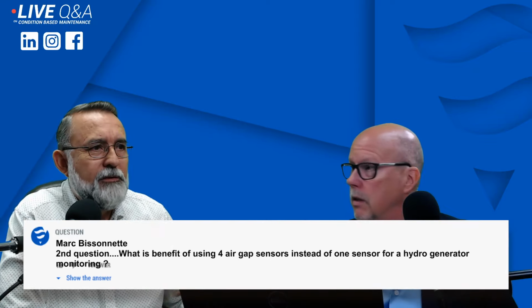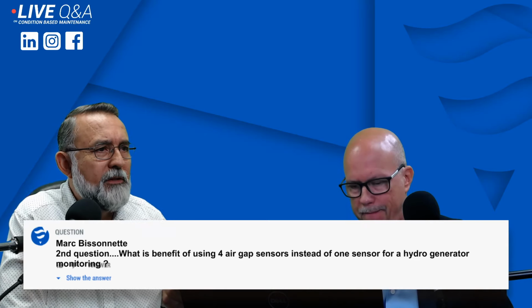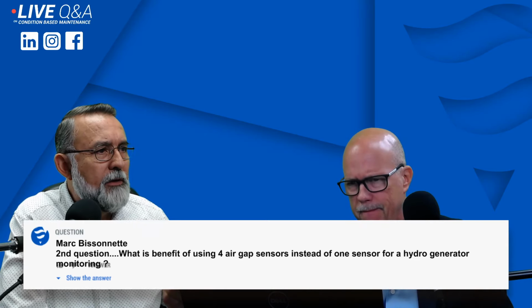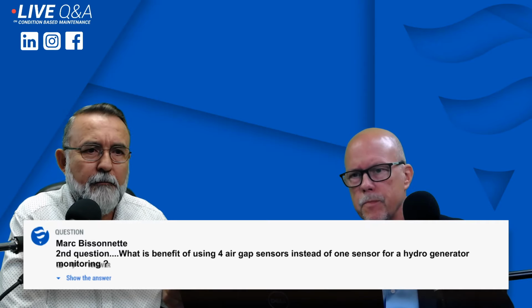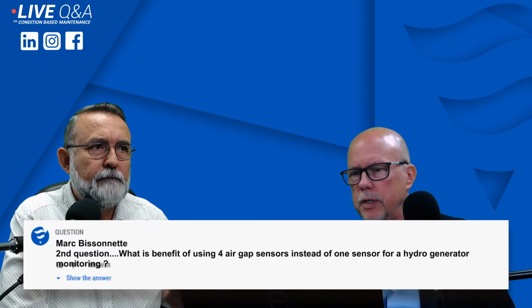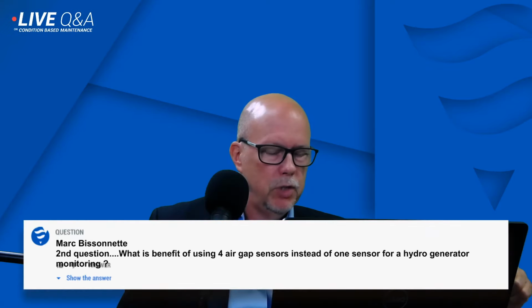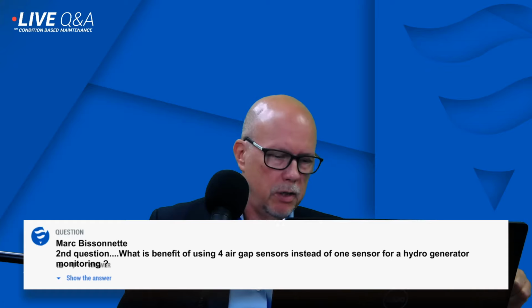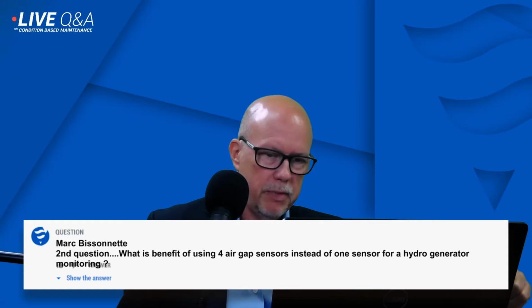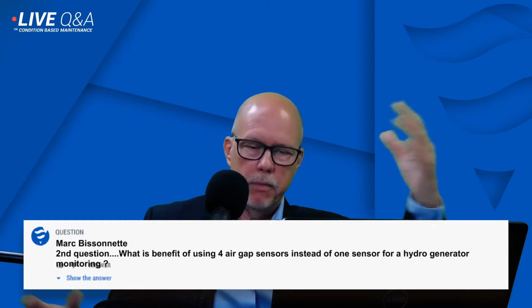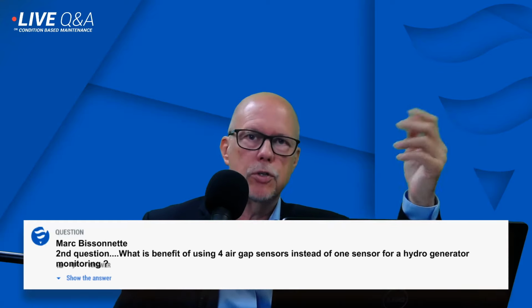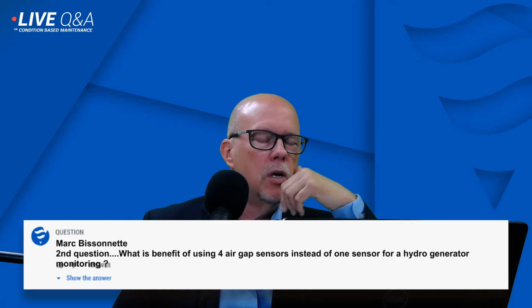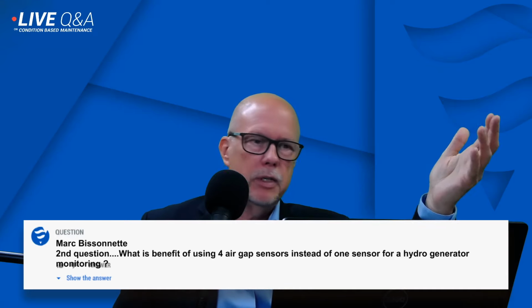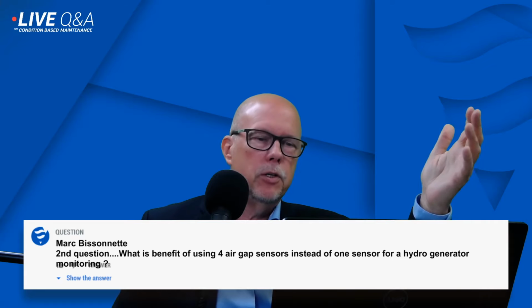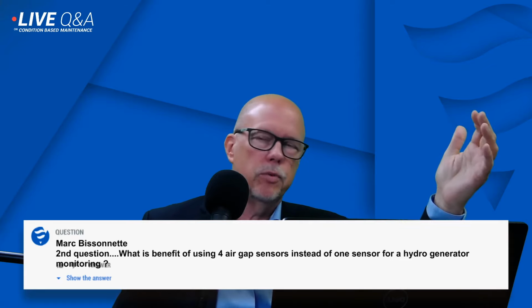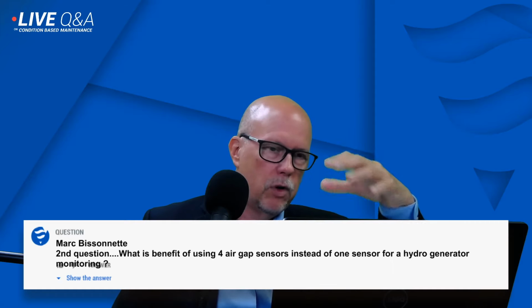We have another question from Mark Bissonnet. Second question, what is the benefit of using 4 air gap sensors instead of 1 sensor for hydro generator monitoring? Well, we have our own specification where we would like to have the air gap sensors give you the best possible coverage. If you have a very big stator, I know cost is always an issue, so people say, well, we'll just use 4 and we'll be able to monitor. But if your unit has a diameter of 12 meters, you'll have large sections of the stator without any coverage. So 4 is for small units.